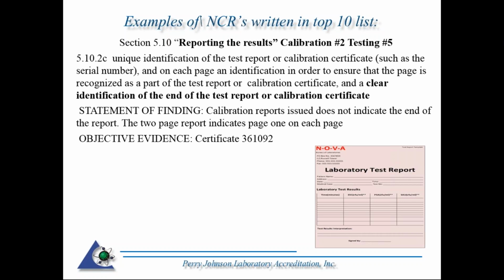If you look at the person who releases the report, quite often it specifies in the standard the name and function. I've written some nonconformances because the function was not identified. This is the person that actually releases the report. In smaller organizations, that could be the same individual that did the particular test or calibration. However, that function needs to be listed.